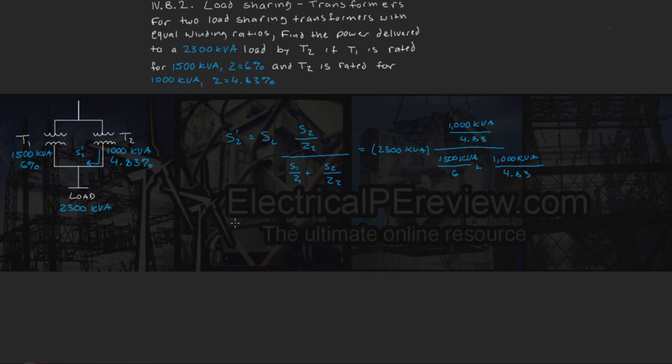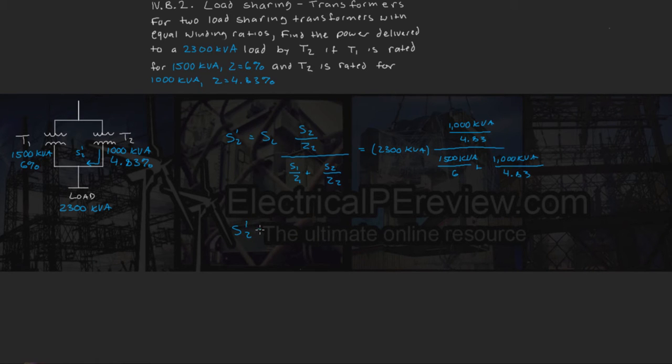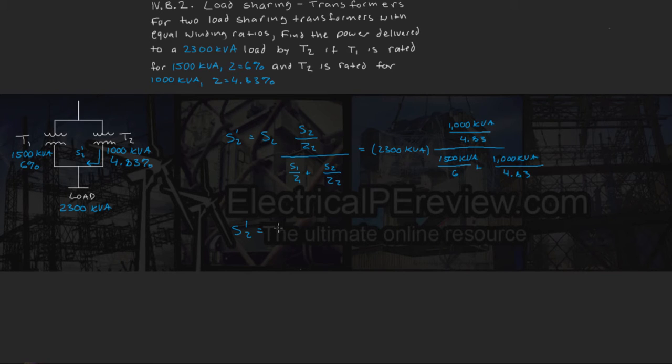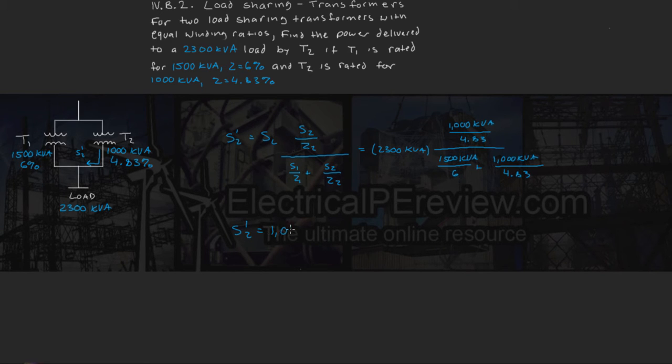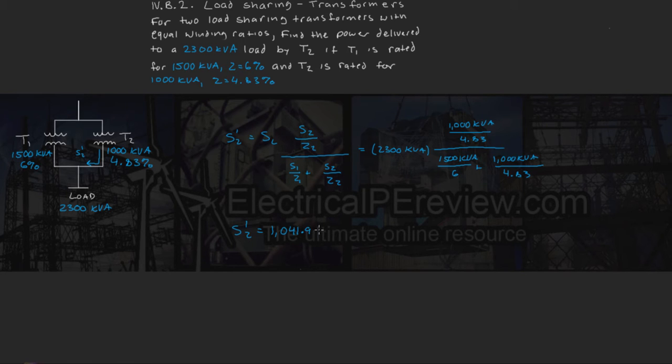So we carry out the math, and we have S2 prime, or our power contribution from transformer 2 to the shared load is equal to 1041.9 kVA.